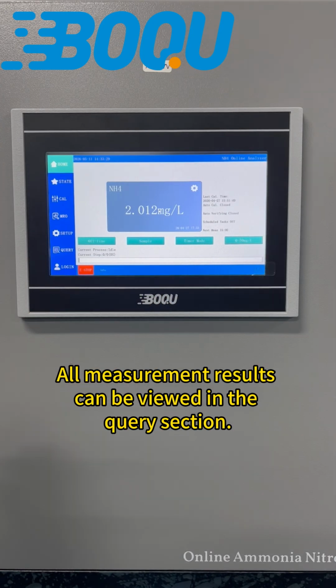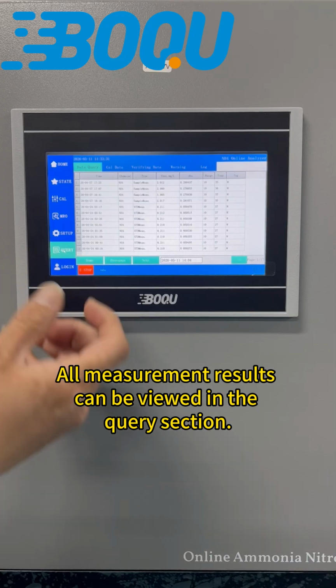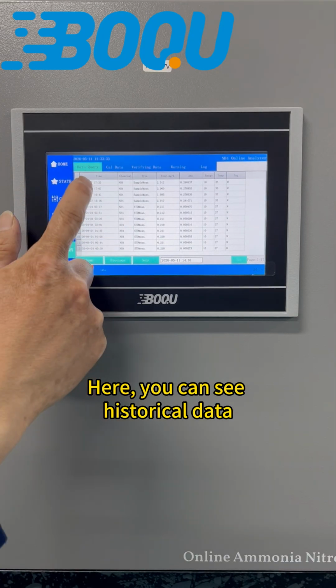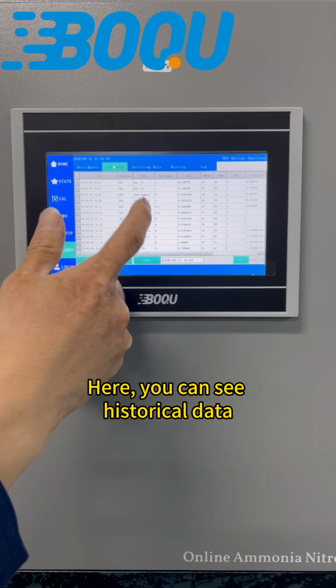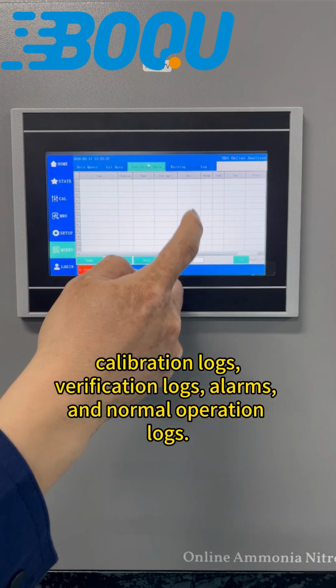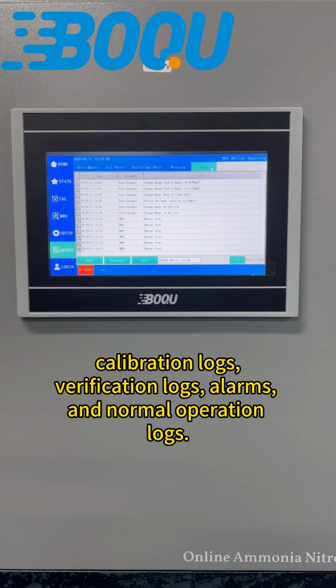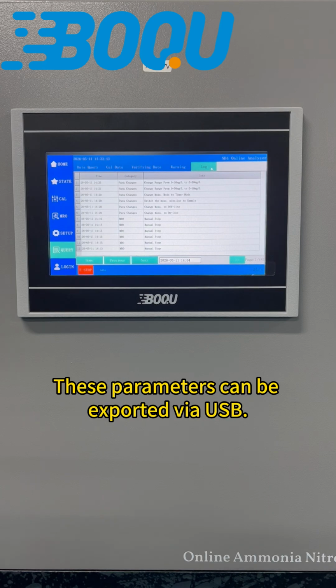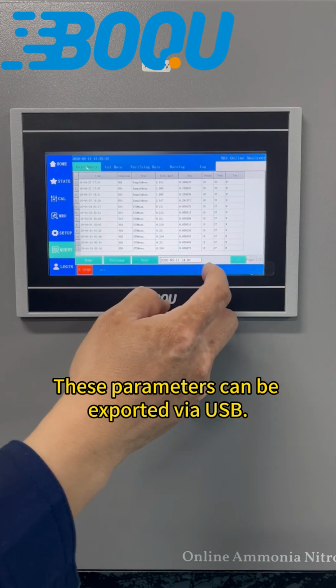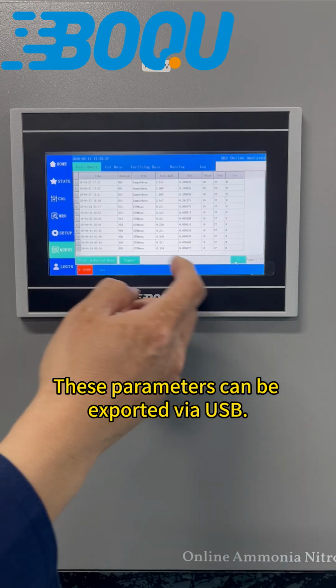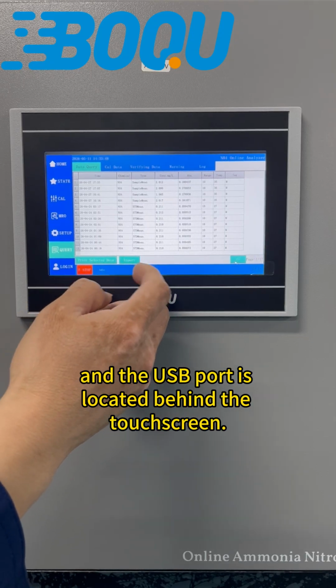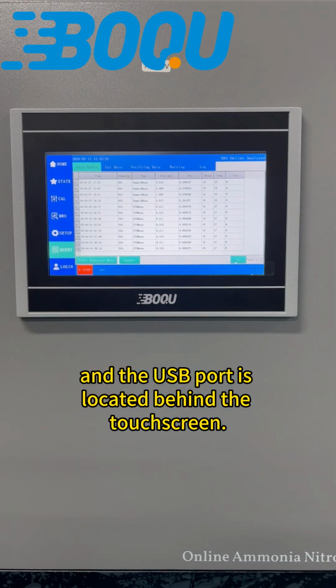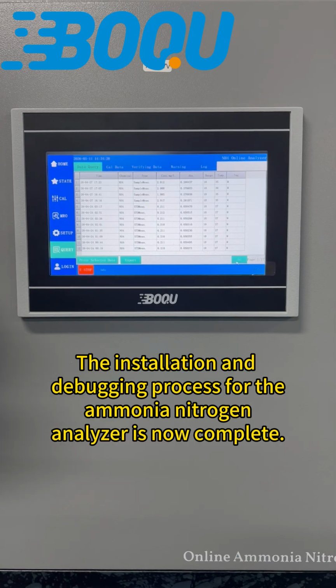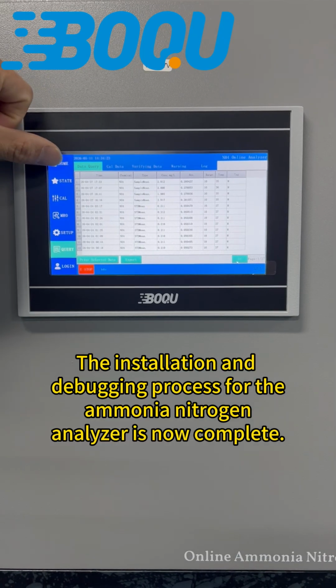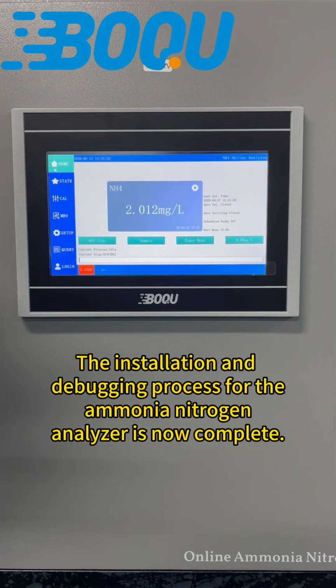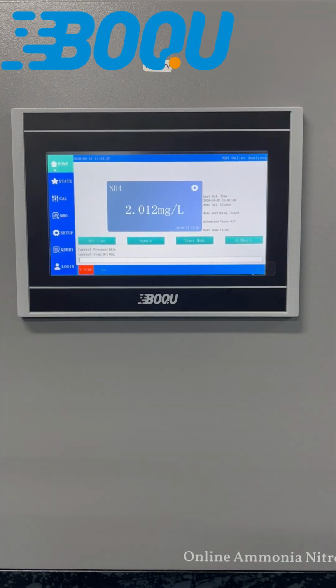All measurement results can be viewed in the query section. Here, you can see historical data, calibration logs, verification logs, alarms, and normal operation logs. These parameters can be exported via USB, and the USB port is located behind the touchscreen. The installation and debugging process for the ammonia nitrogen analyzer is now complete.